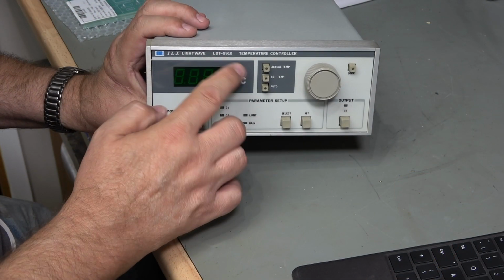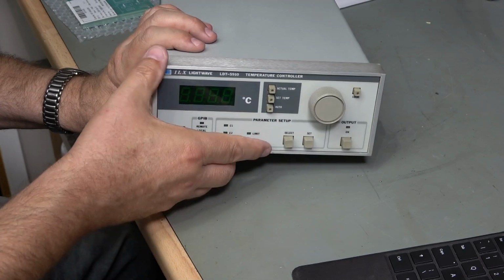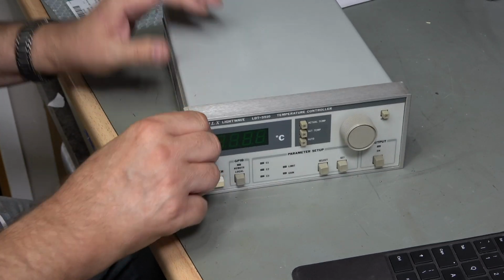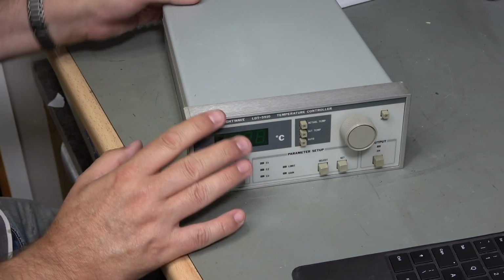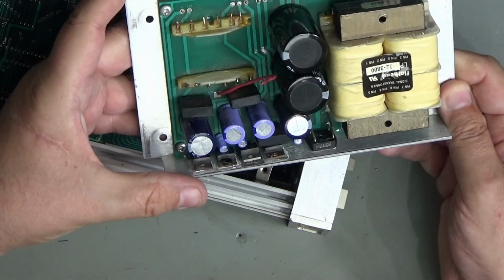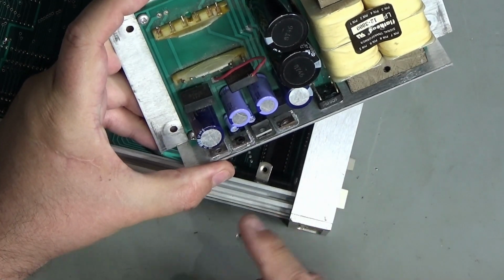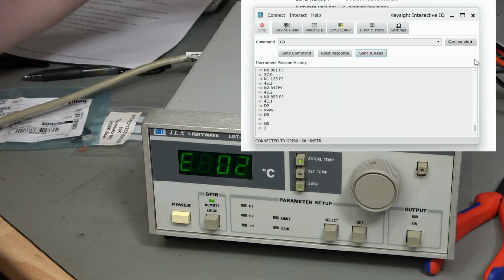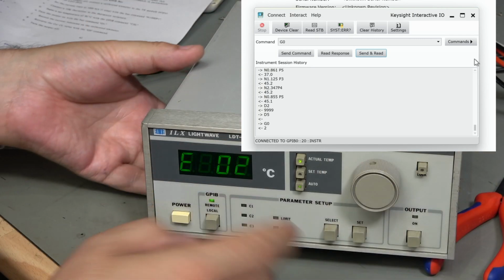Hi, it's time to take a look at this ILX Lightwave LDT-5910. It's a thermoelectric temperature controller similar to the more advanced 5910B that I fixed a few months back. I originally thought the fault was limited to a smashed power supply board, which is just like the last one I repaired, but starting calibration quickly revealed a fault in the resistance sensing.